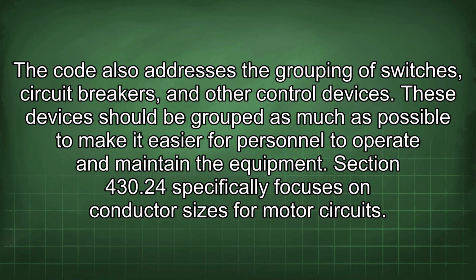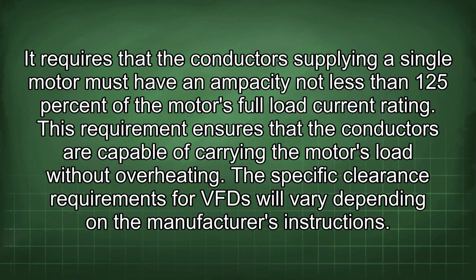Section 430.24 specifically focuses on conductor sizes for motor circuits. It requires that the conductors supplying a single motor must have an ampacity not less than 125% of the motor's full load current rating. This requirement ensures that the conductors are capable of carrying the motor's load without overheating.